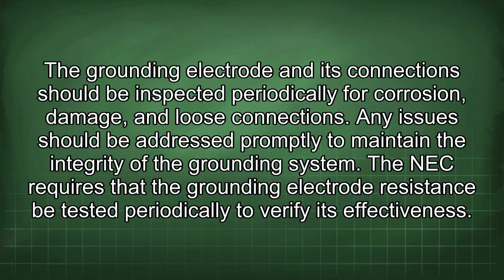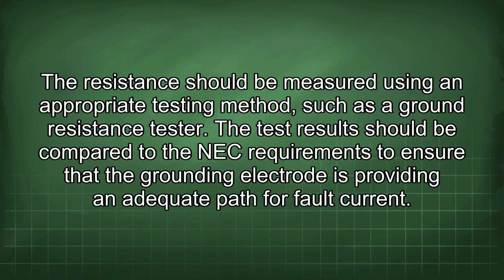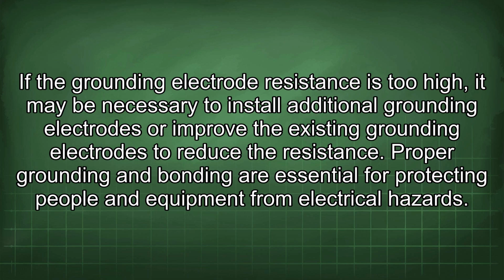The NEC requires that the grounding electrode resistance be tested periodically to verify its effectiveness. The resistance should be measured using an appropriate testing method, such as a ground resistance tester. The test results should be compared to the NEC requirements to ensure that the grounding electrode is providing an adequate path for fault current. If the grounding electrode resistance is too high, it may be necessary to install additional grounding electrodes or improve the existing grounding electrodes to reduce the resistance.